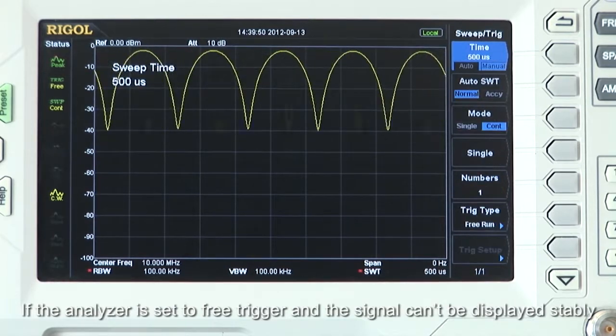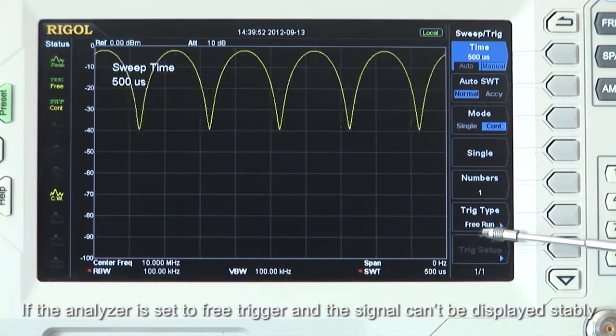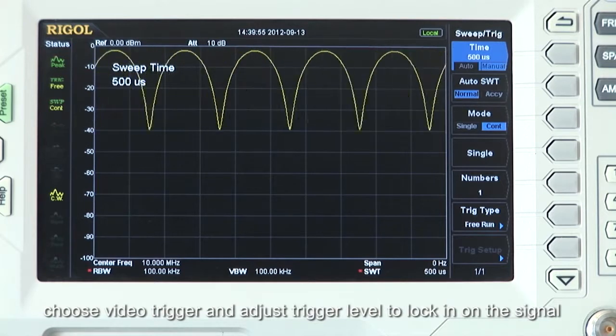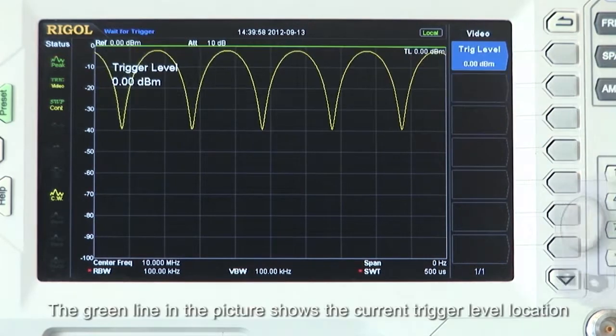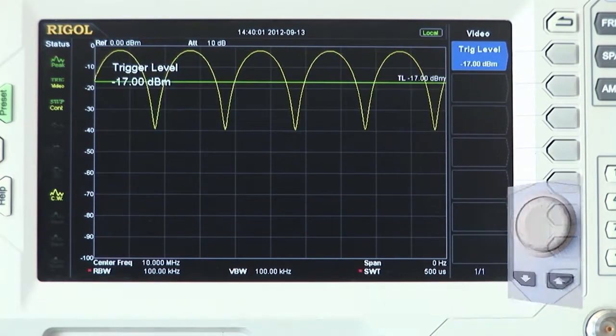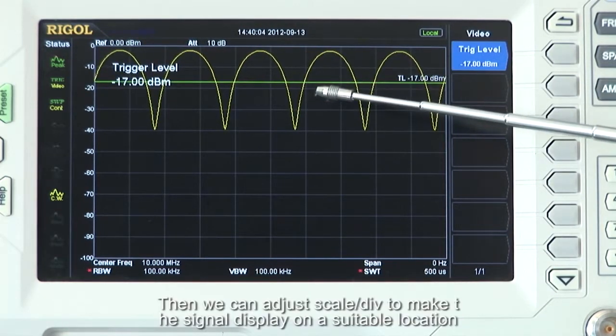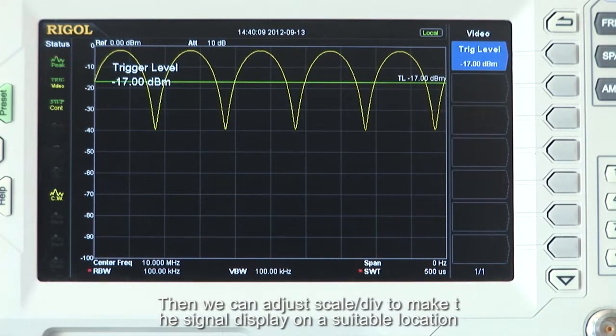If the analyzer is set to free trigger and the signal can't be displayed stably, choose video trigger and adjust the trigger level to lock in on the signal. The green line in the picture shows the current trigger level location. Note that the trace has now been triggered stably.